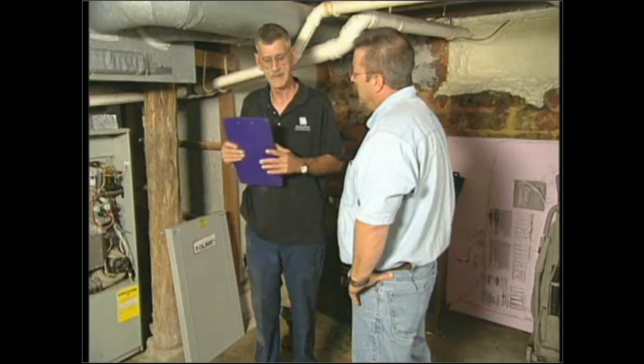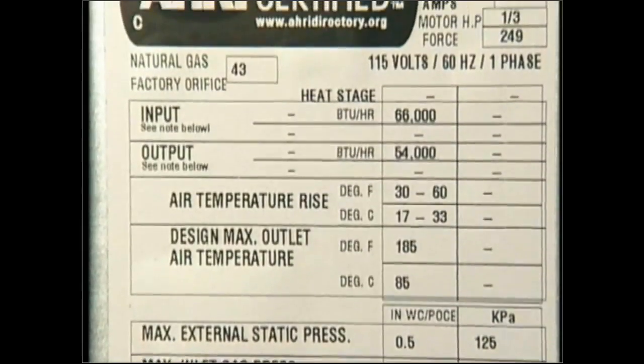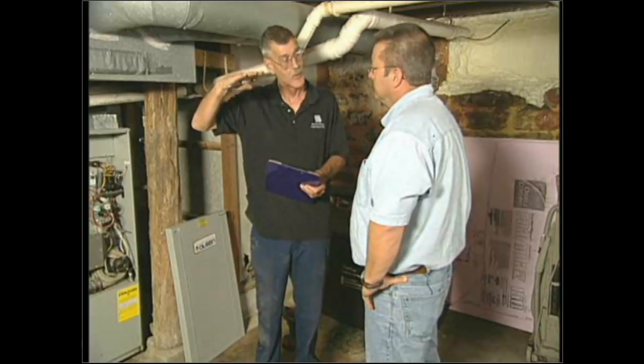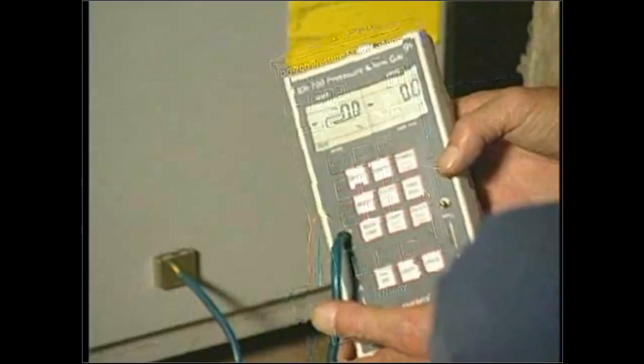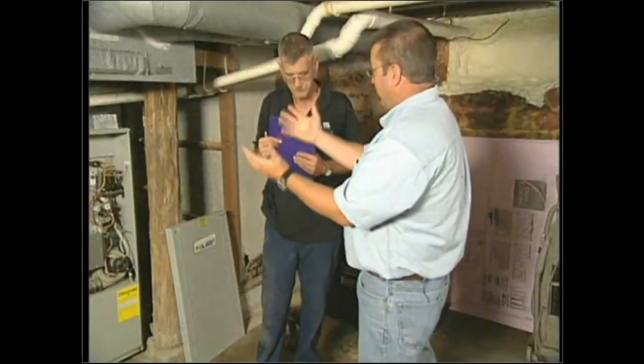Since my static pressure is a little high and my flow rating is just about right — at 1,000 CFM for a 90,000 BTU furnace — all I need to do is correct my return air pressures a little to make the furnace work easier. One of the biggest complaints from homeowners is that the furnace is loud and the air is cool. We take the flow test, compare to the BTU rating, take a temperature rise test and a static pressure test — all three together. If static pressure is high, CFM is high, and temperature rise is low, I can lower the fan speed to lower static pressure, which brings temperature rise up into the proper range, giving the homeowner warmer air at a slower rate with less noise.